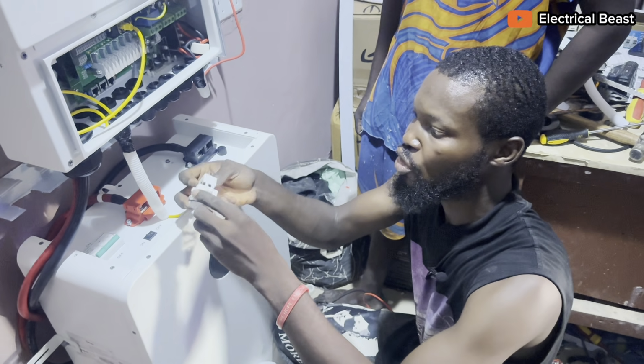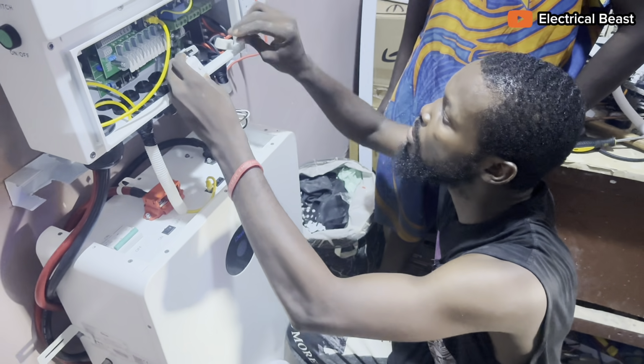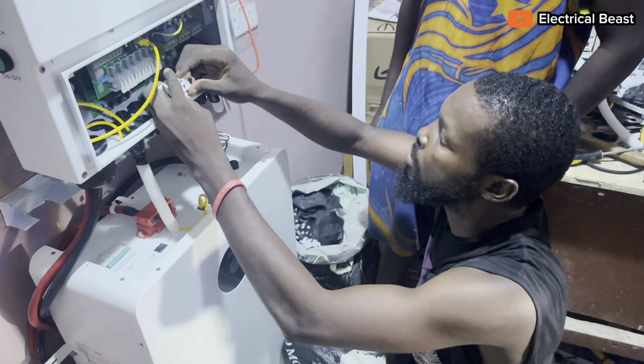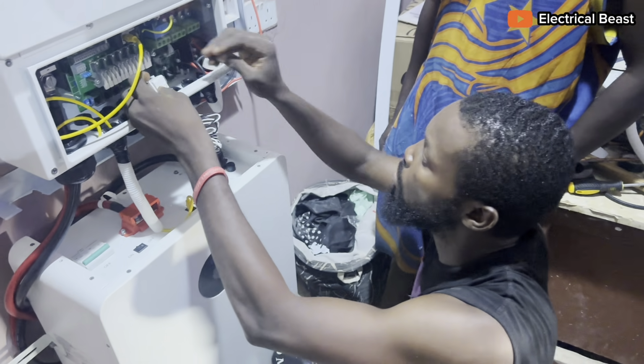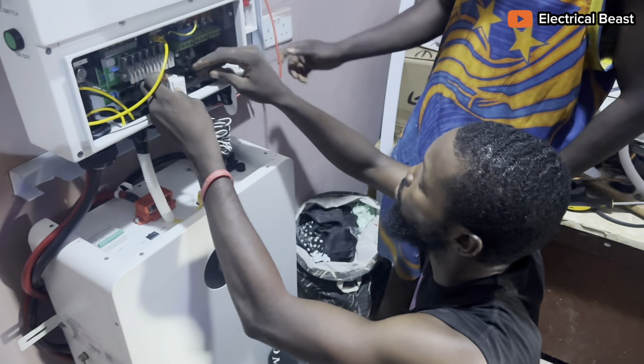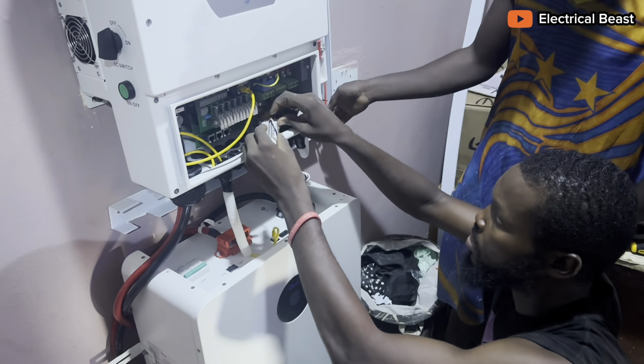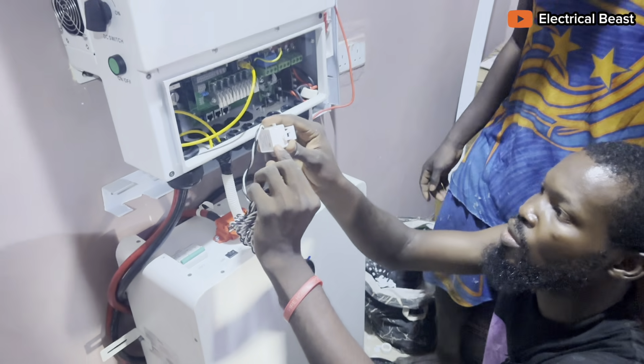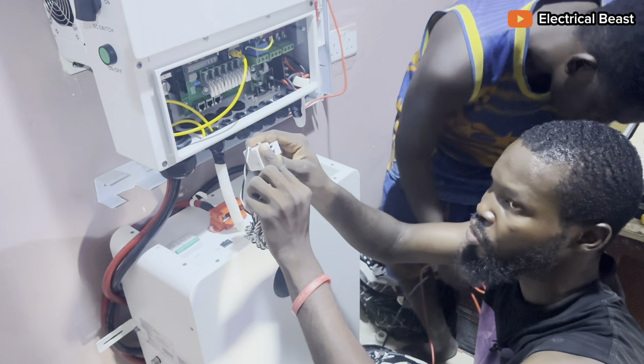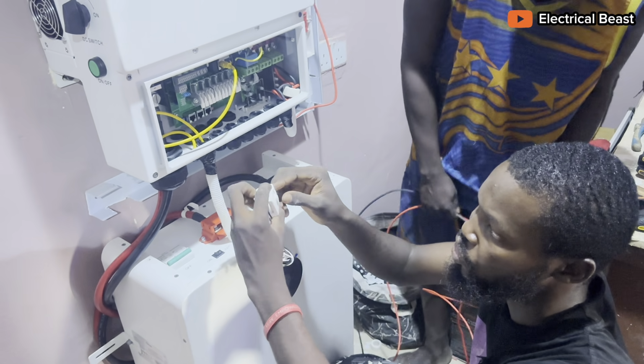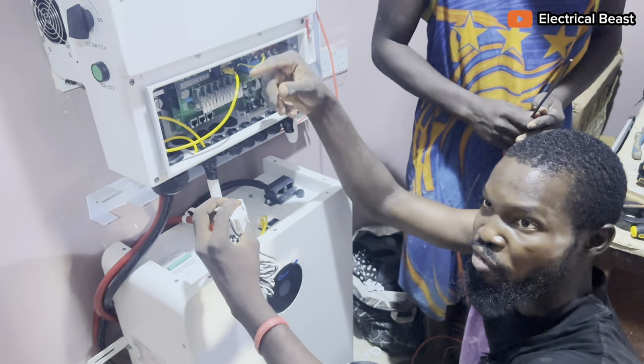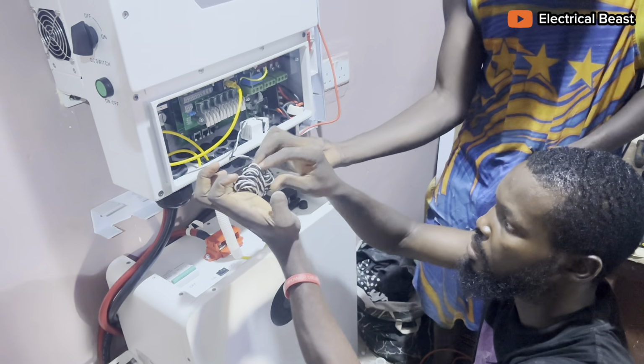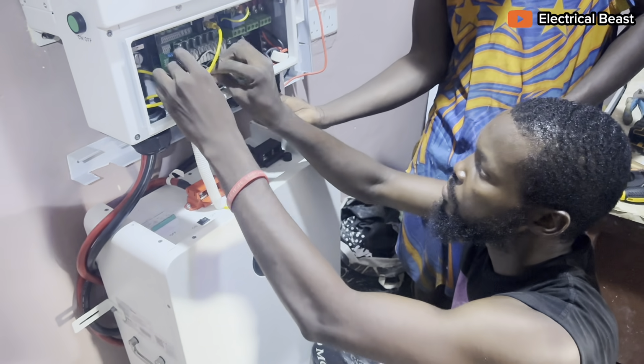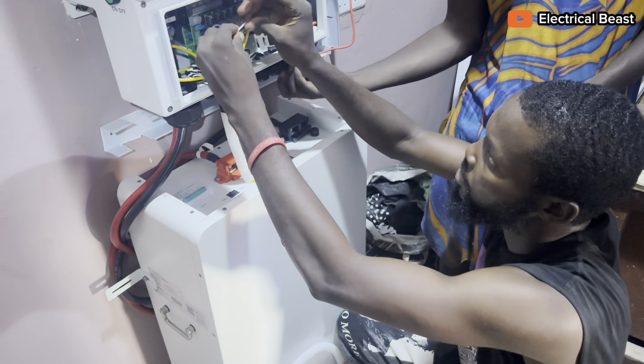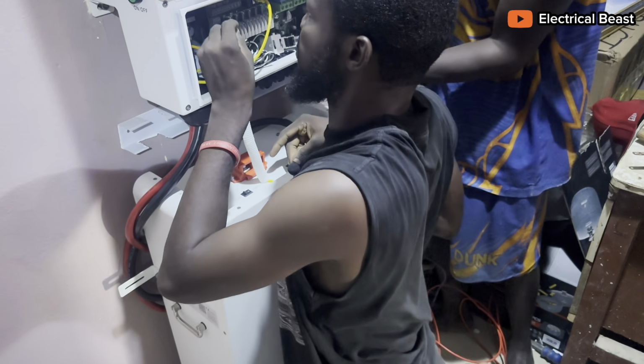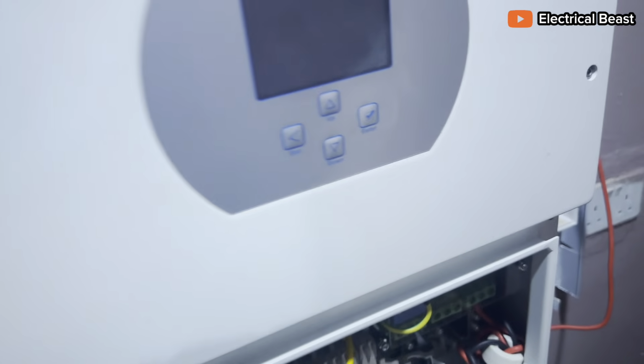And so I'm going to make sure you connect the CT to the input side, the positive side of the input. So here's the input. Connect it to the positive side. Then make sure this arrow faces up, the direction the current is supposed to flow. So the load is going to flow to the inverter from the grid. It's going to flow out of the inverter. So that's that. Then the wire, I'm going to connect it to 5 and 6 in this address bus here.